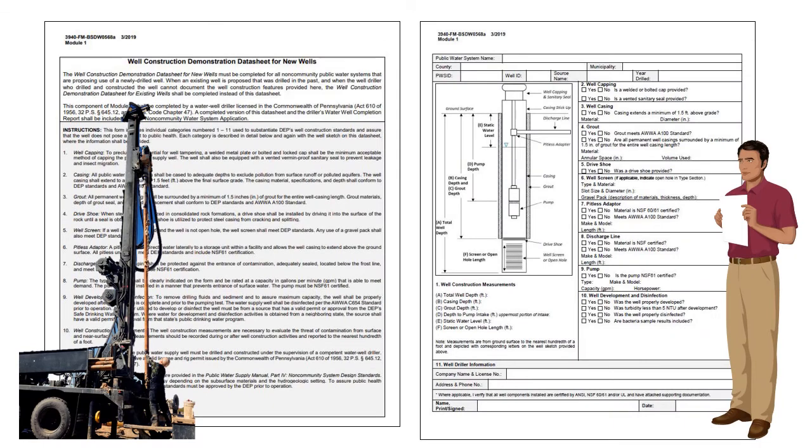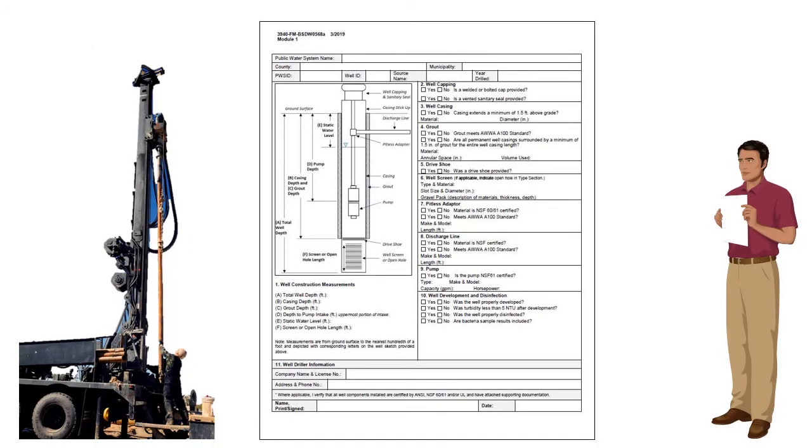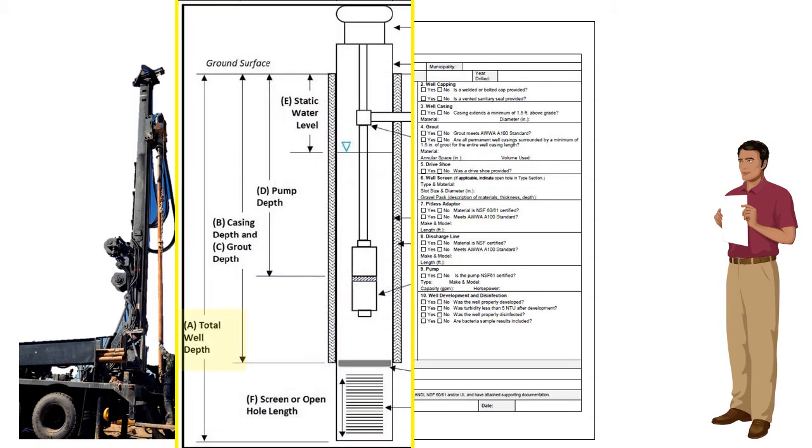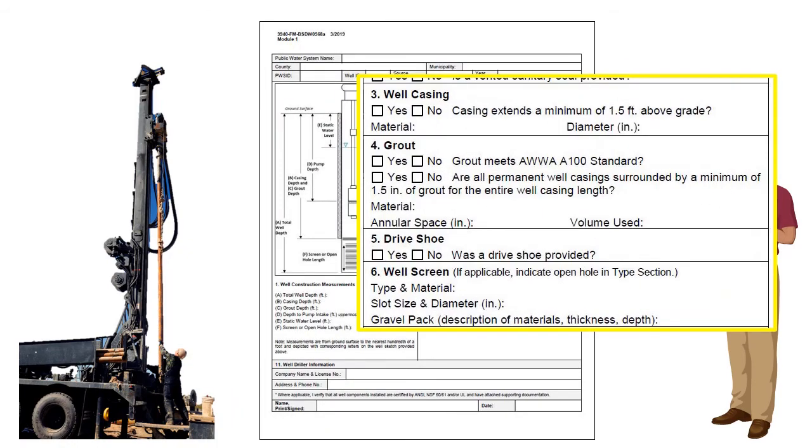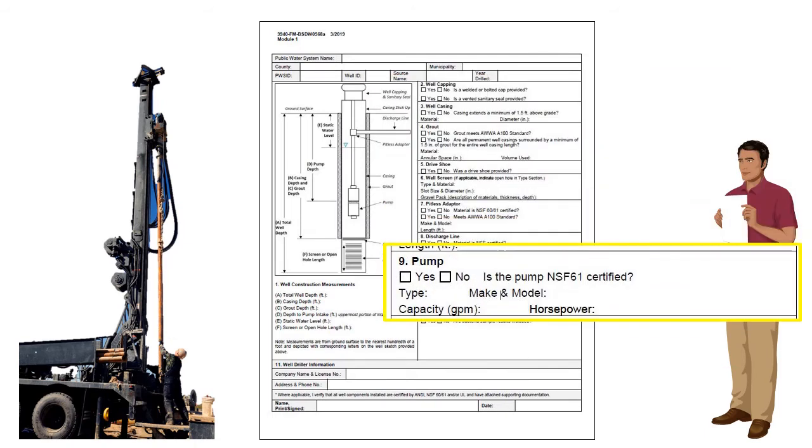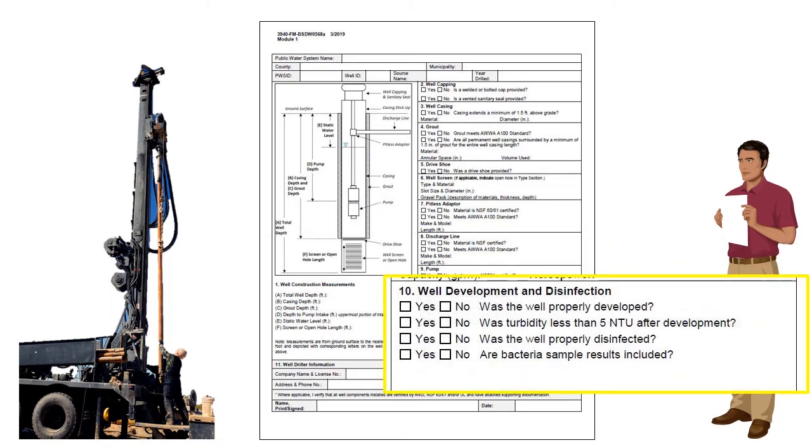The form and well construction sketch provide information necessary for the DEP review staff to assess if the well is constructed to standards and in a manner that is protective of public health. Specifically, the form asks for details on the following well construction features: well construction measurements of total well depth, casing and grout depth, depth to pump intake, static water level, and depth to screen or open interval; well capping, well casing, grout, drive shoe and screen, pitless adapter, discharge line, pump, and whether the well was properly developed and disinfected and any bacteria or turbidity issues.